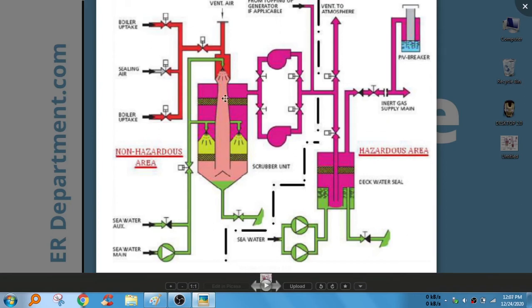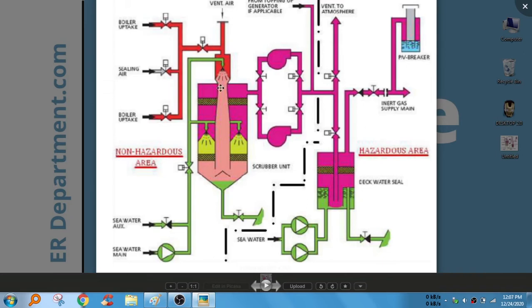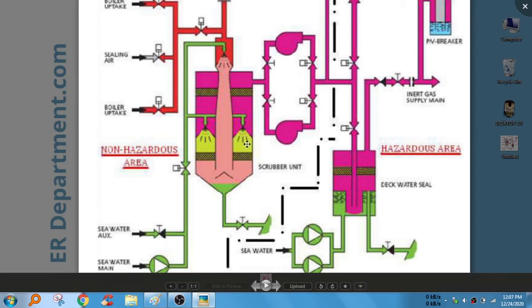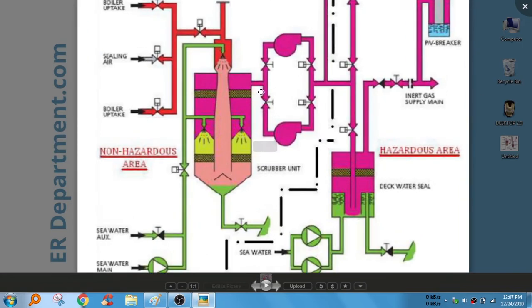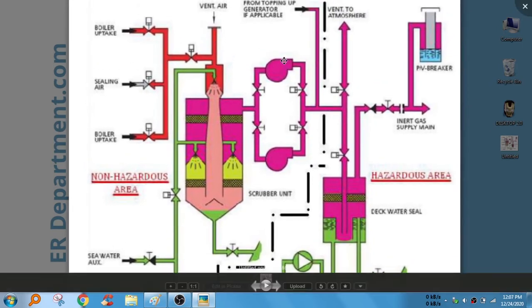If there is any impurities in the flue gas, this sea water dissolves it. See what the sea water does: it removes the heat and it cleans the flue gases. So it goes through these measures, you can see here there are measures provided. This is for when the flue gas goes through this tortuous path, it gets more cleaned.